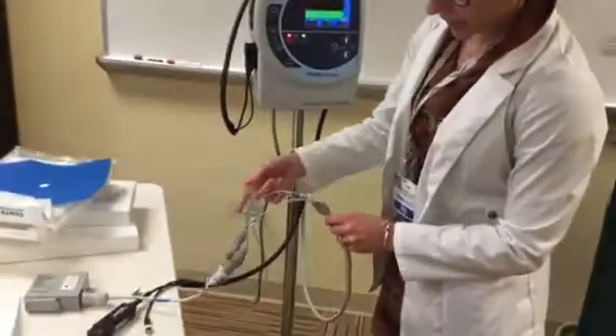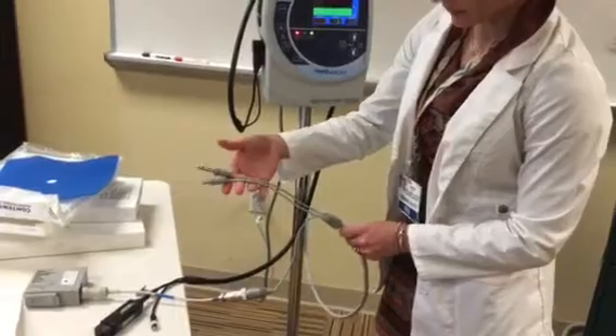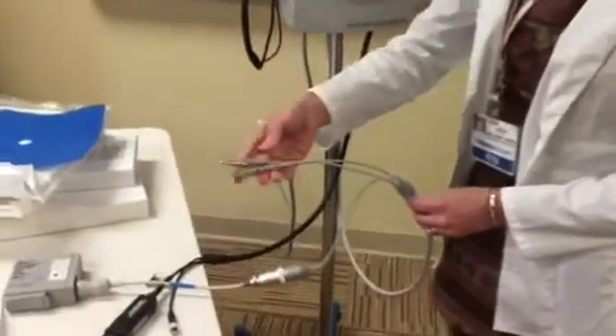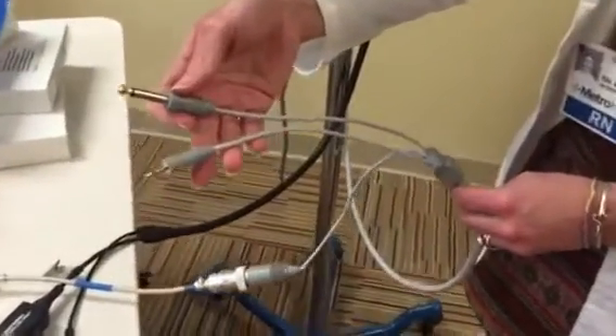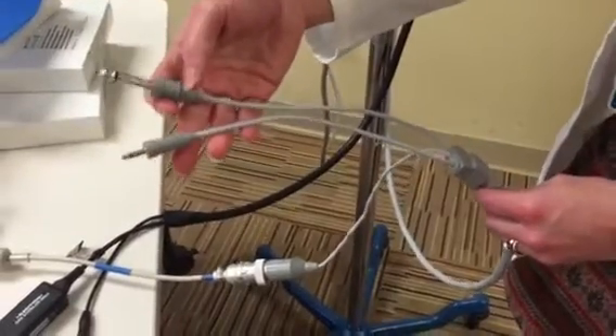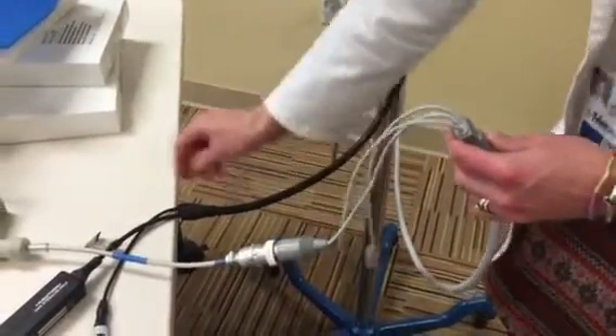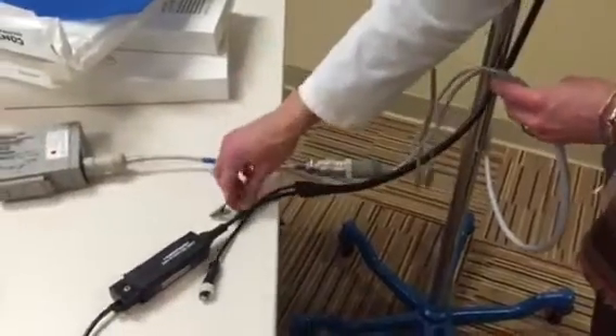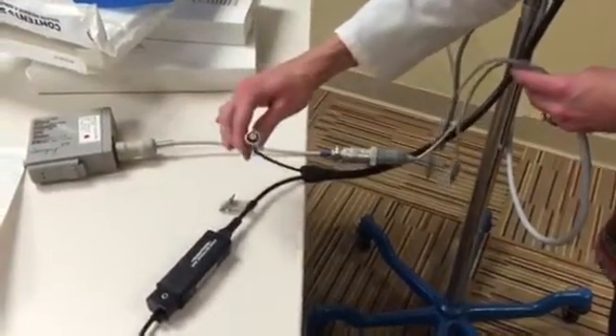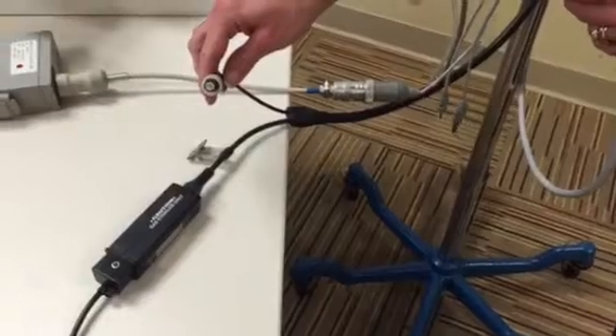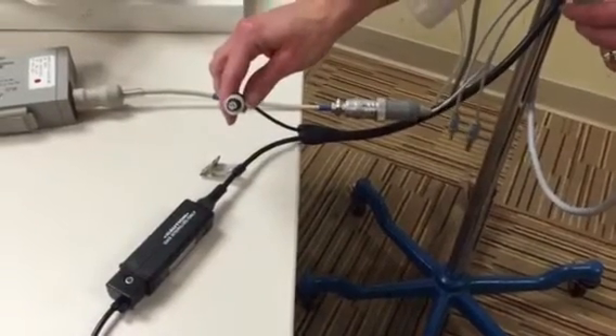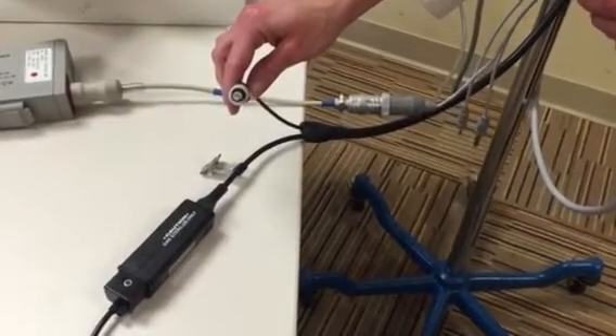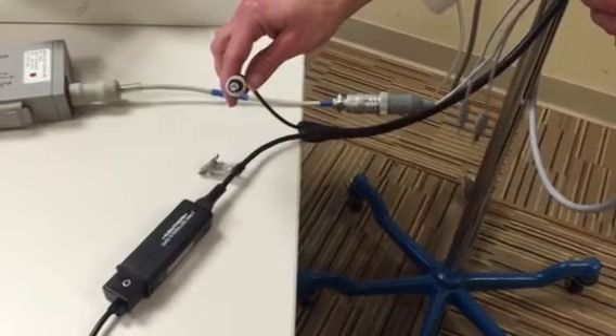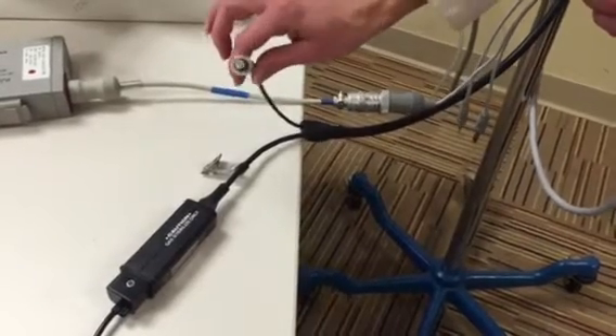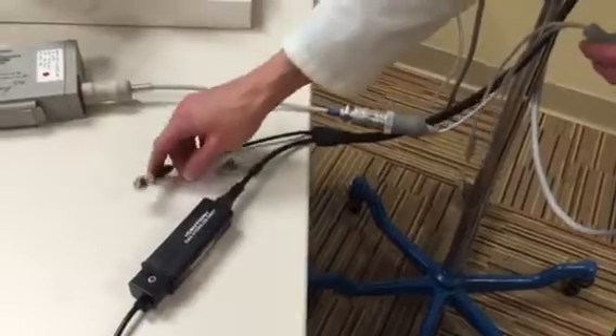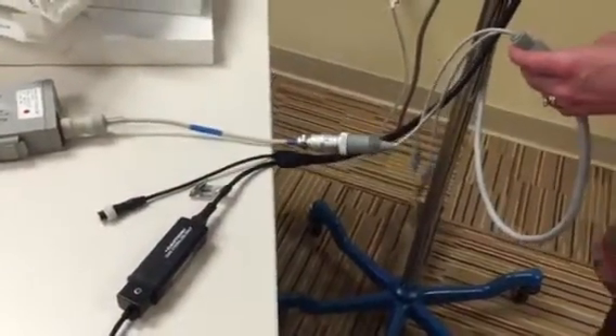And now we're going to take a quick second before we move on to talk about all these different pigtails that are hanging off here. These we do not use. They will not be connected to anything. We don't use the functionality that these offer. Similarly, down here by the preamp cable, this little part is the temperature connector. So we do not stock Camino fiber optic catheters that are capable of measuring intracranial temperature, but that's what that connector would be for. So that will never be connected to anything either.